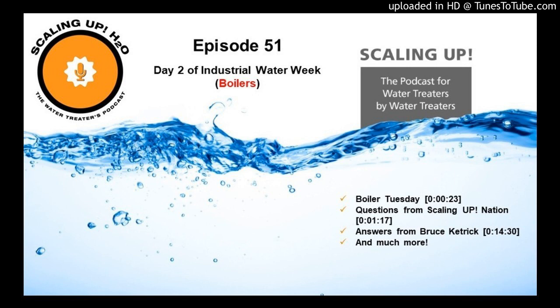Only a few of the dispersants like PCA or some of the amps actually will tolerate those temperatures without breaking down. And in most cases, it's high purity water, very little, if any, alkalinity, usually like a positive 10 OH, but can be as little as 1. The chemistry is almost purely coordinated phosphate situations where you measure the phosphate versus the molar sodium in the boiler.